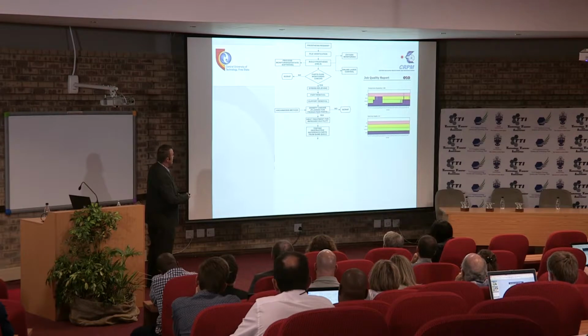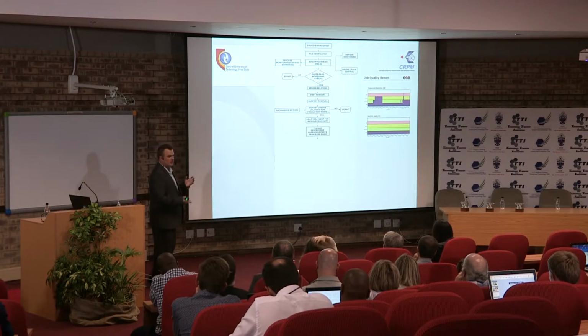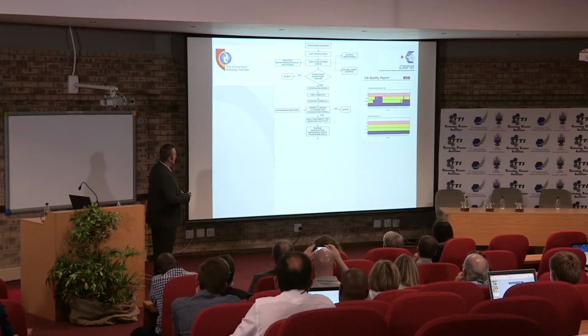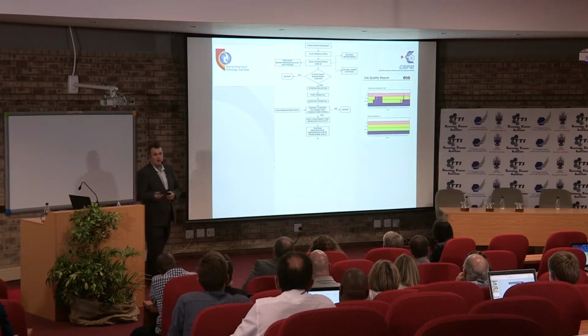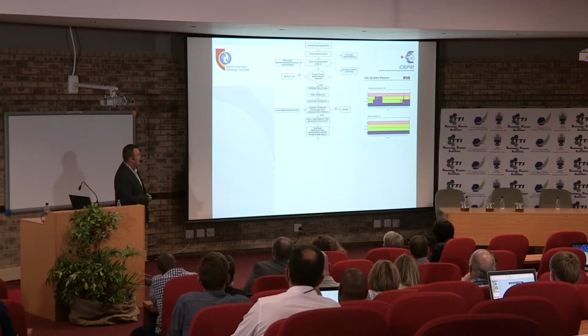Okay, just on how our certification framework looks. You will have a prosthesis request, then file verification. A lot of standard operating procedures had to be written for each step, data preparation, all of that, to verify that the quality is good going into the machine. We have basically monitoring software. You can see there's a copy from EOS. We are logging the oxygen, online laser control. You go through all these checks.